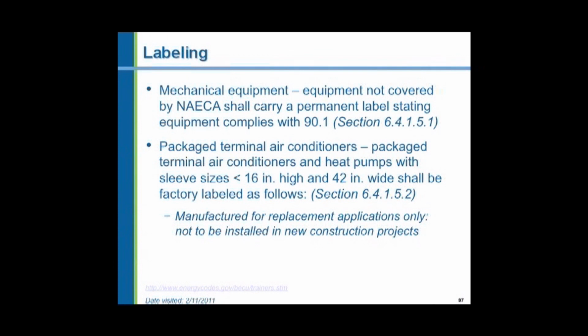Now there's an interesting exception to the new energy efficiency requirements, and it's for little bitty PTACs. Tiny air conditioning and heating units don't have enough space in them to have large enough evaporator coils and condenser coils to get the efficiency that the code now requires. But the people writing the codes understand that there are literally millions of them in existence in the United States, in buildings, and they fail. They have an actuarial life of somewhat less than 15 years.